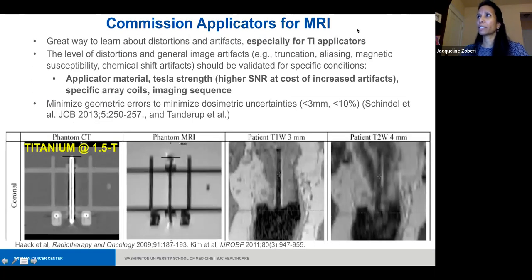Commissioning the applicators for MRI is a great way for the brachytherapy physicist to learn about distortions and artifacts, especially for titanium applicators. The level of distortions and general image artifacts should be validated for specific conditions, including applicator material - is it plastic, is it titanium - what Tesla strength, what coils are we using, what imaging sequence is it. You've got to evaluate for these different conditions, and the goal is to minimize these geometric errors because in the end we want to minimize dosimetric uncertainties.